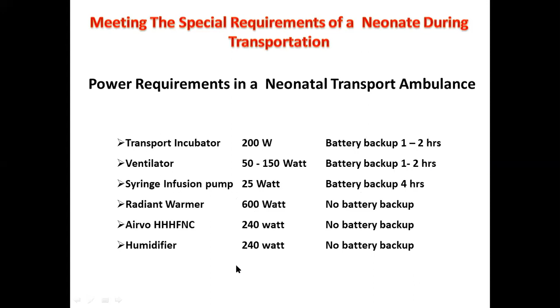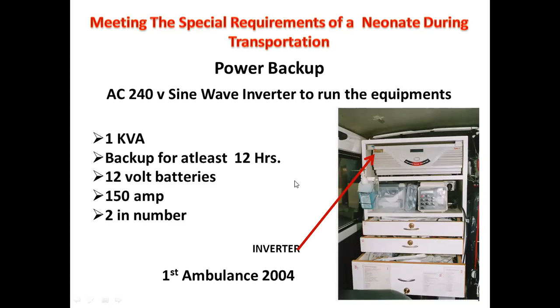So you can see the huge power requirement, and this isn't just for 1 hour - it continues for 5, 6, 7 hours at times. So a sine wave inverter has to be installed, because sine wave means you avoid fluctuation while supplying power. At least a 1 kVA sine wave inverter is needed, and our aim should be to keep a backup of at least 12 hours - it may not happen practically, but that should be our aim. So we use 12-volt batteries, 150 amperes each, 2 in number - that's the minimum we need. We have to find a place to put these batteries - the inverter doesn't occupy much space, but the batteries do occupy a lot of space.